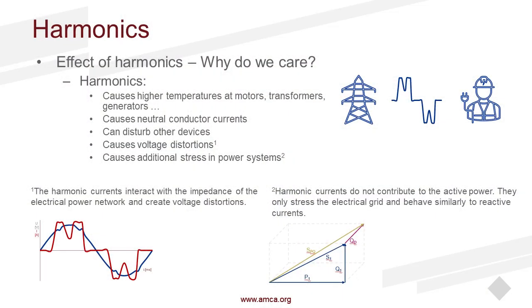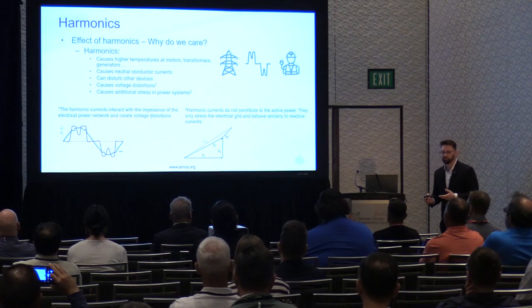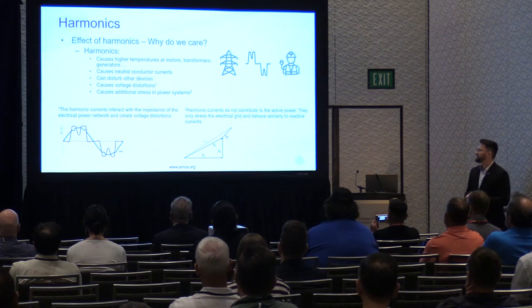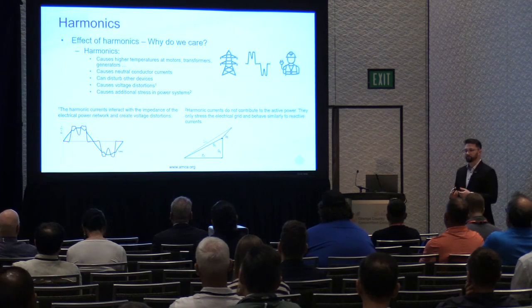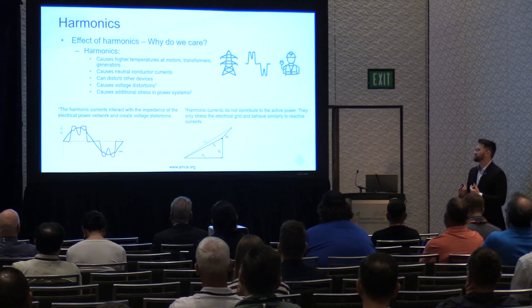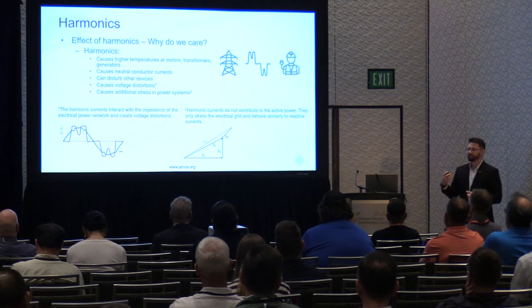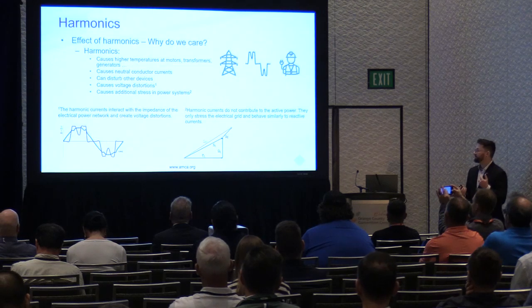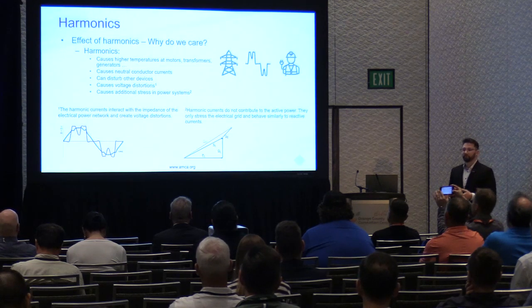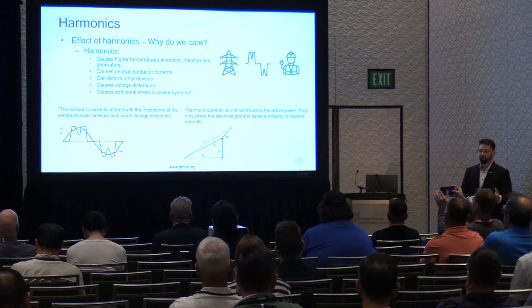So why do we care about harmonics? So harmonics can do a lot of different things, and I think it's relatively new that we've figured out about harmonics, that we're learning more about harmonics and what they can do. Usually you see higher temperatures within your motors, generators, your transformers. You're seeing fuses blown. You're seeing circuit breakers trips. You're seeing different equipment on your site that's just not working properly. It's not working efficiently.